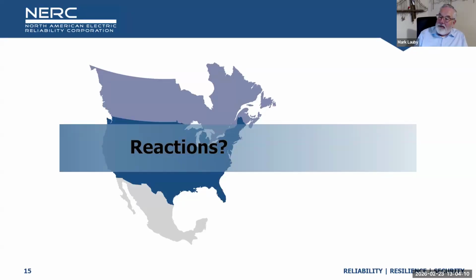You kind of got to step back and figure out, well, what do these big machines give me? And when I take the big machines off, what do I need to substitute it with? For example, frequency response was buttressed by inertia of the machines. Rather than having that, can we use batteries and fast injection of energy? So sitting back and saying, what do I need it to be doing? I need it to be damping the system. And there are inverters that can provide power damping. Again, nobody's building those into the system, or maybe they have the capability but they're not turned on.